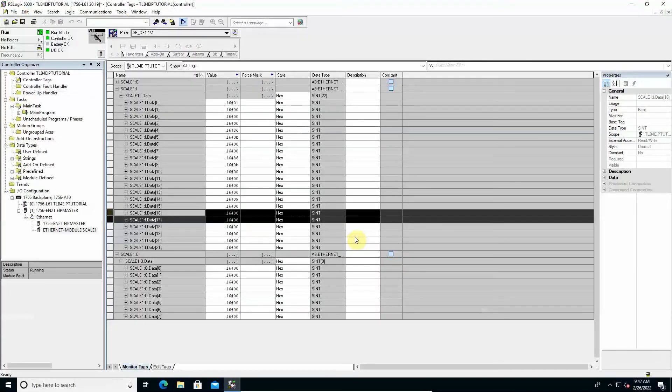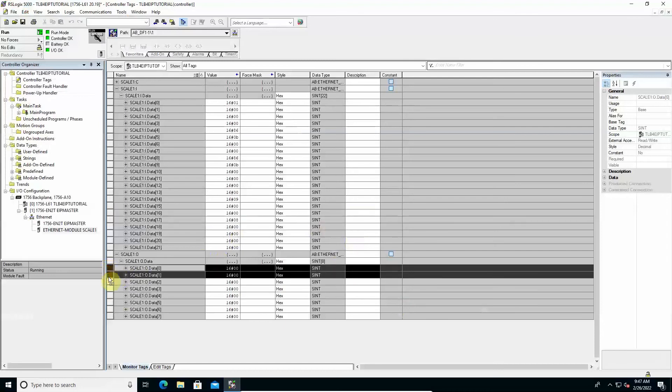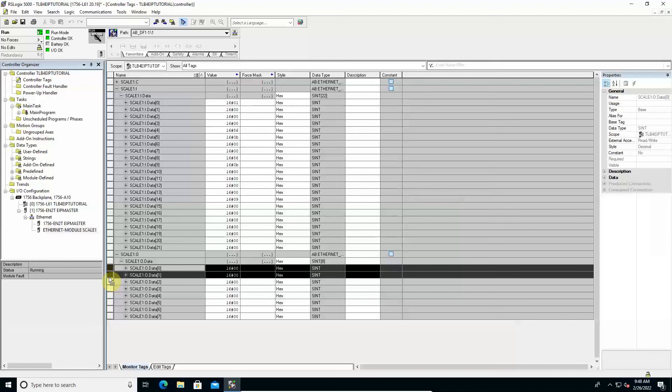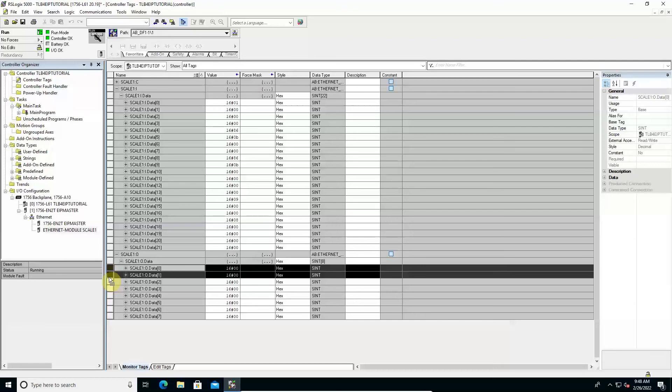Among the data output from the PLC it is useful to focus especially on the command register. This 2 byte value is used to send specific numeric codes to the instrument, each of which corresponds to a request for execution of a specific operation. All the numerical codes allowed and the relative associated operations are available in the protocols manual. For example we can test the operation of the command codes for the semi-automatic tare operation. Code 7 to perform semi-automatic tare and Code 9 to remove the previously applied semi-automatic tare.